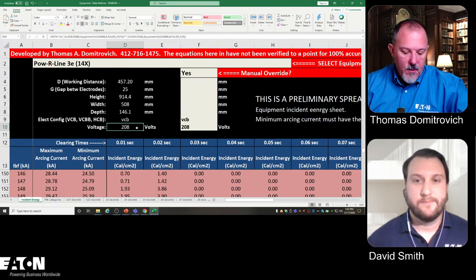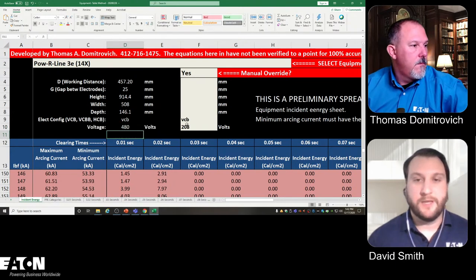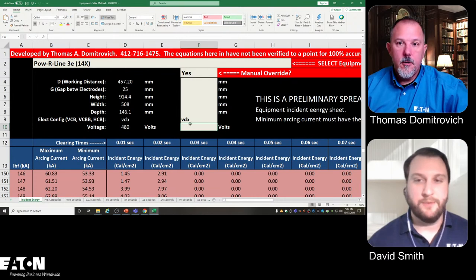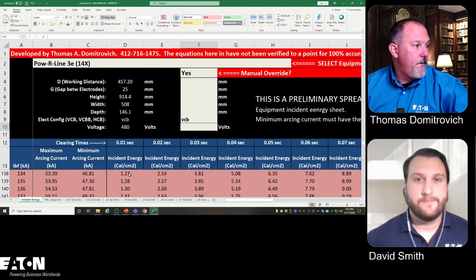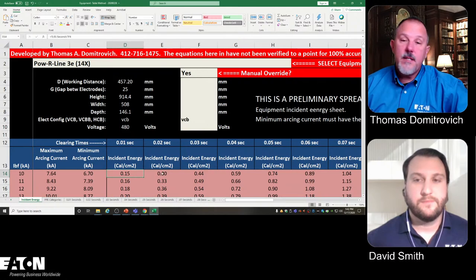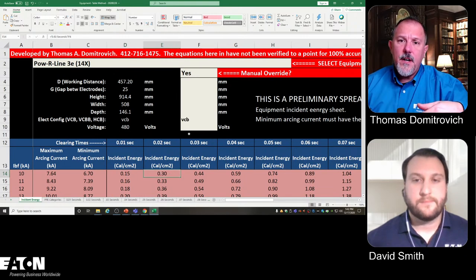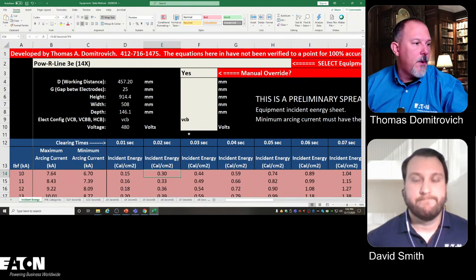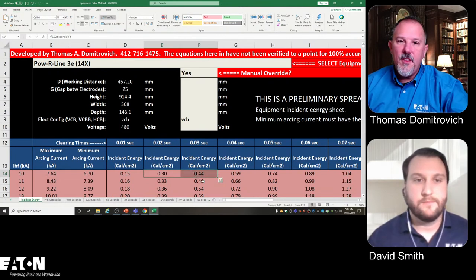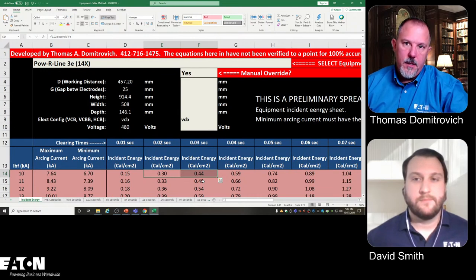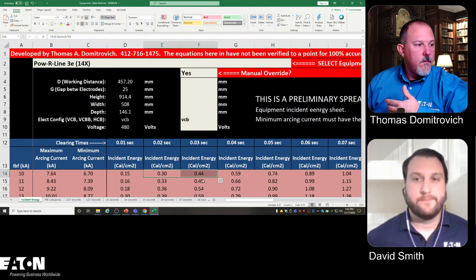I've got my voltage. Let's put my voltage back up to 480. Yeah, that's what we were talking about before. Whoever asked about voltage, this is where it comes into play. Exactly. So now, if I have 10,000 amps of available fault current, and my clearing time is a typical instantaneous around 0.02 seconds, right? 0.016 is one cycle, so a cycle and a half, two cycles, somewhere in that ballpark. So somewhere in here is where you're going to clear. The incident energy is going to be around 0.3 to 0.44 calories of the amount of energy that I'm going to let through to that downstream.